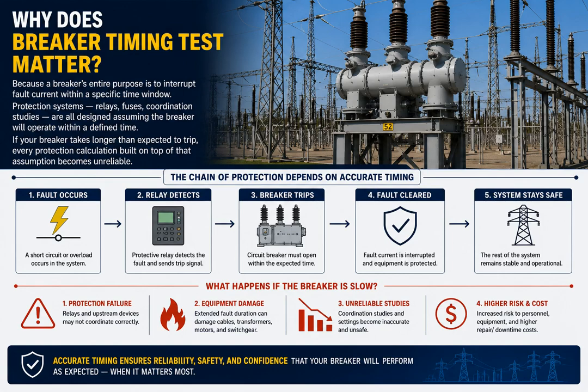Why does breaker timing test matter? Because a breaker's entire purpose is to interrupt fault current within a specific time window. Protection systems, relays, fuses, coordination studies are all designed assuming the breaker will operate within a defined time. If your breaker takes longer than expected to trip, every protection calculation built on top of that assumption becomes unreliable.